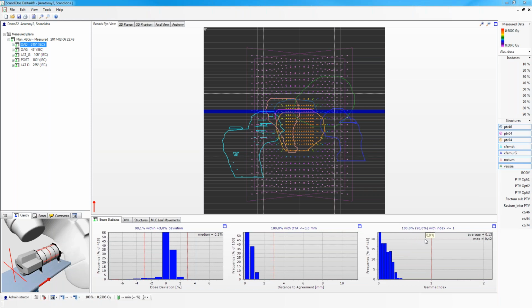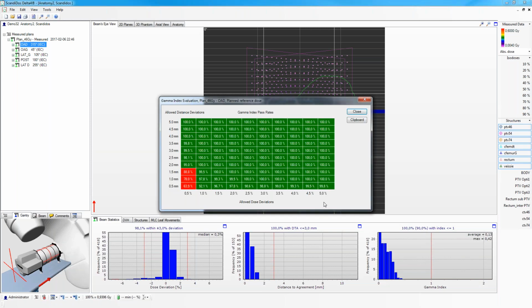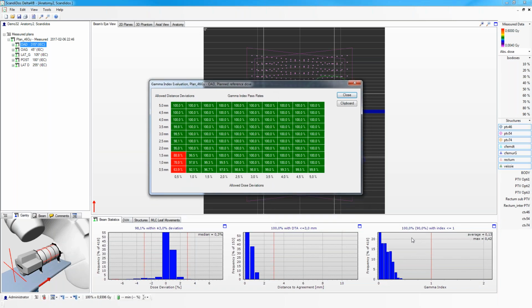The gamma pass rate is displayed for the criteria that you've defined for this particular patient. What I can also do is display my gamma pass rate for a number of different distance deviations and dose deviations. So for example, for this particular plan, I have set the criteria 3% 3 millimeters, and I can see that I get 100% pass rate.